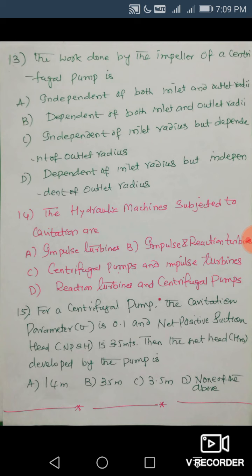Question 15: For a centrifugal pump, the cavitation parameter σ = 0.1 and NPSH = 3.5 meters. Find the net head Hm developed. The relationship is: NPSH_min = σ × H. So H = NPSH / σ = 3.5 / 0.1 = 35 meters. Answer is B.